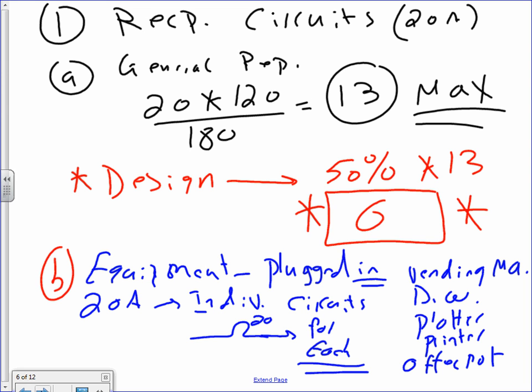Receptacle circuits. Here's the calculation. Now I came up with these numbers based on the following. I have a receptacle circuit. You will be a fool to pull less than a 20 amp receptacle circuit in a commercial building. Do we agree on that one? 15 amp out the window. Doesn't exist. Can I? Yes. Should I? No. Why? Because it's foolish. You're losing copper. You're putting a lot of copper for nothing. So a 20 amp circuit, that's my cutoff.